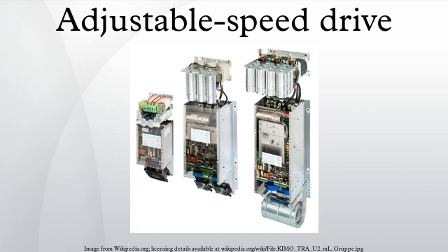The motor develops the torque required by the load and operates at full speed. The output shaft transmits the same torque to the load, but turns at a slower speed. Since power is proportional to torque multiplied by speed, the input power is proportional to motor speed times operating torque, while the output power is output speed times operating torque. The difference between the motor speed and the output speed is called the slip speed. Power proportional to the slip speed times operating torque is dissipated as heat in the clutch.